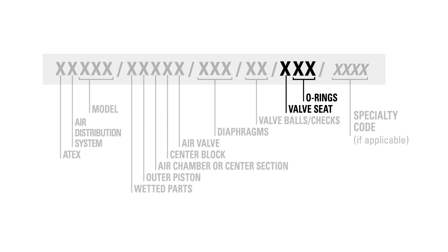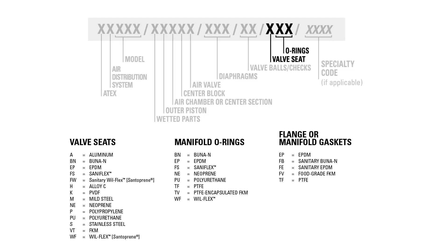The fifth section of the model designation denotes the valve seats and O-rings used in the pump. This section can be either two or three digits long depending on the seat selected. In the case of a pump with an elastomeric seat, this section will only have two digits, as elastomeric seats do not need a manifold O-ring. The Buna N, denoted as BN, and Wilflex, denoted as WF, are examples of elastomeric seats that do not need an O-ring. In the case of a pump with metallic or plastic seats, this section will be three digits: the first digit denotes the seat material and the second and third digits denote the manifold O-ring material. For example, ATF in this section would denote an aluminum seat identified by A, and PTFE O-rings identified by TF.